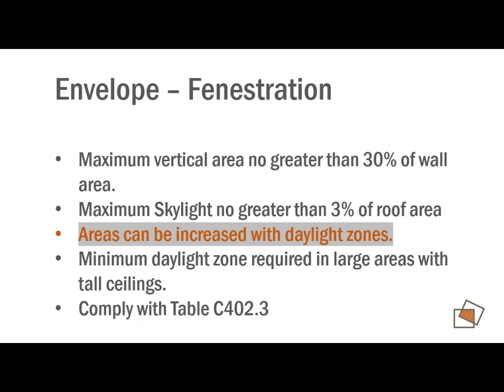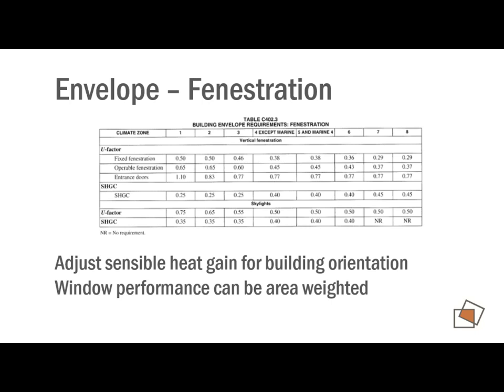And then we've got another table, which is just spelling out our required U-values and solar heat gain coefficients that are required for all your windows and skylights, all your different fenestration. It allows for an adjustment. If you have a north-facing window or a certain overhang, it lets you bump the solar heat gain coefficient up. You can allow a little more heat and light through your window. It's just kind of a common sense thing. If you have north-facing glass, it's not going to hold to quite the same standard because it's not going to see the sun.